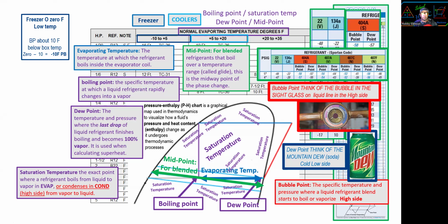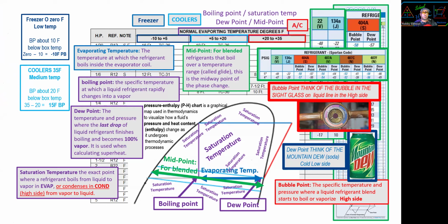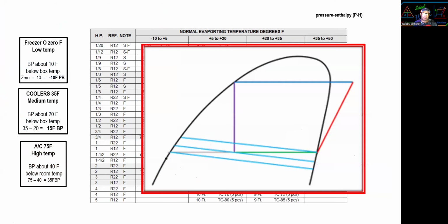For refrigeration, the boiling should be about 15. Refrigeration boiling temperature is about 20 below box temperature. Why? 35 minus 20 equals 15. And for air conditioning, the boiling point should be about 40 degrees below room temperature. Room temperature 75 minus 40, 35 degree boiling point. Okay, I hope this makes sense a little bit. We'll cover it again later.